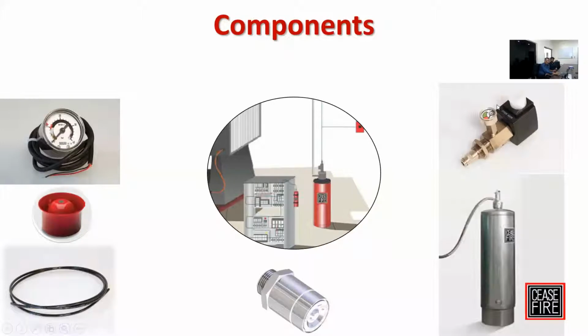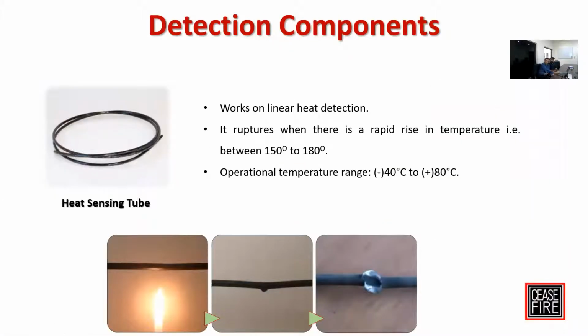So these are the components for the system. Now coming to the heat sensing tube, this works on linear heat detection. Anywhere along the entire tube, if there is a rise in temperature, it will rupture. Once it is ruptured, it will create a pressure differential, and once the pressure differential is created, the valve will be actuated automatically. So that's the heat sensing tube.